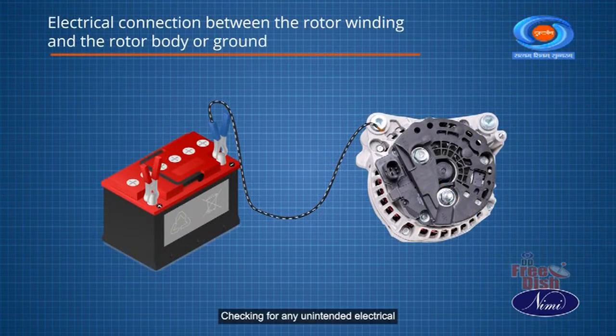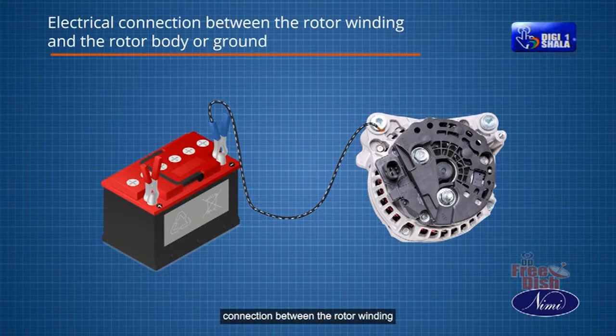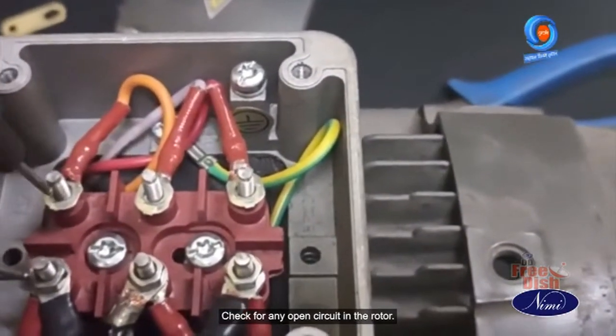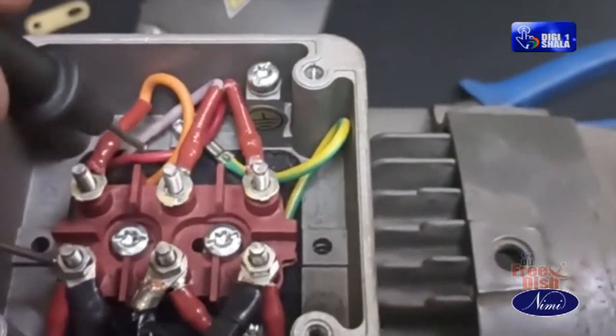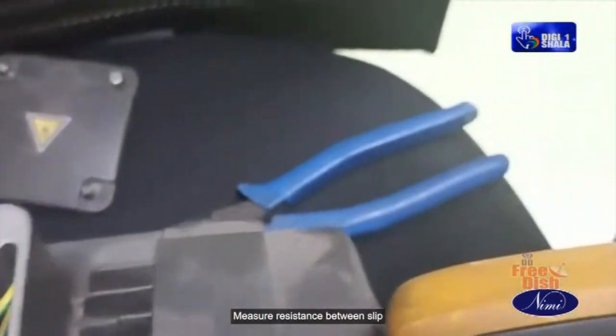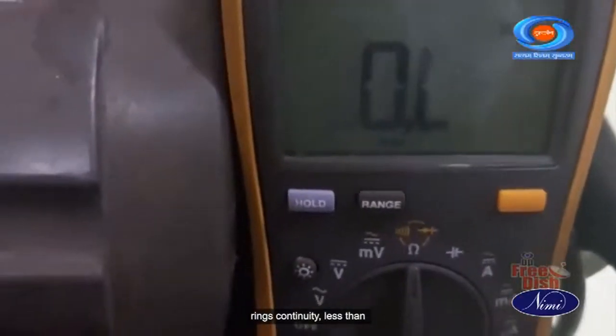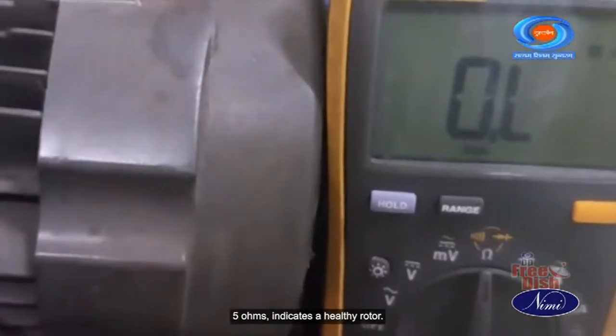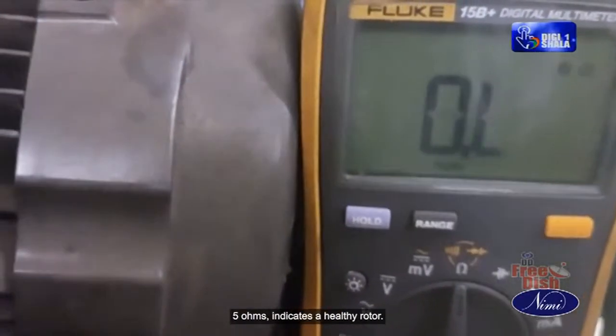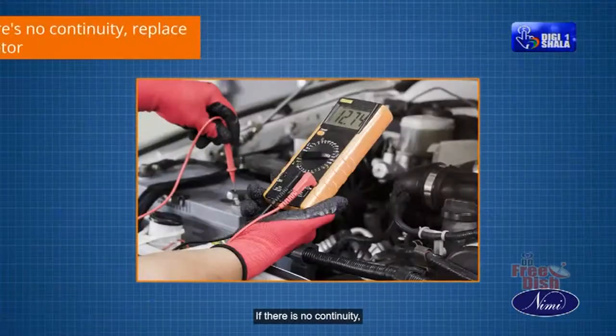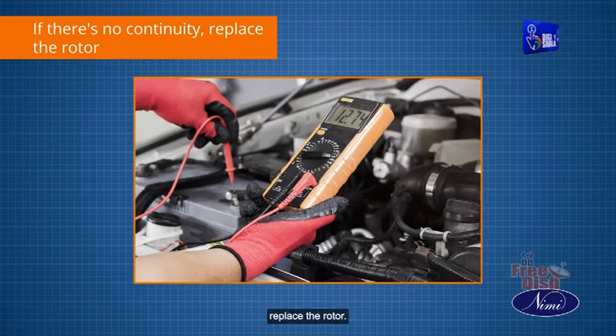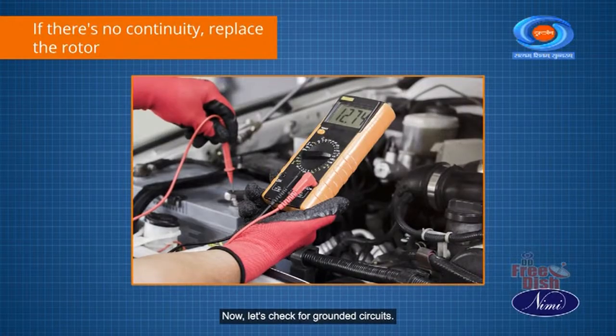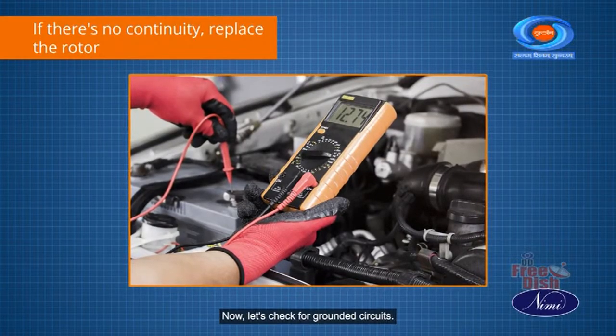Checking for any unintended electrical connection between the rotor winding and the rotor body or ground. Check for any open circuit in the rotor. Measure resistance between slip rings; continuity less than 5 ohms indicates a healthy rotor. If there is no continuity, replace the rotor. Now let's check for grounded circuits.